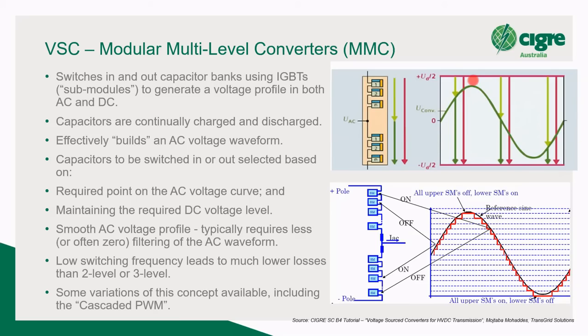and you want to create 200 kV positive and negative, what that means is you have to have 100 capacitors switched in at any one time. Now, if you want a zero crossing, I've got to switch in 100 of these capacitors to make up 200 kV. So if I switch in 50 at positive and 50 at negative, then they'll negate each other and we'll have a zero crossing. And that's what the converter does.